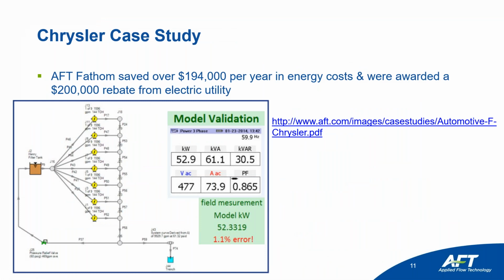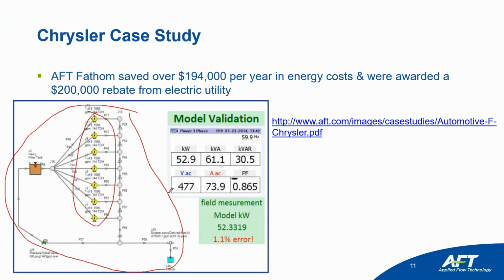Okay, so a few case studies that I want to go over. This is a case study that was done for the Chrysler plant in Michigan, in the United States, and they built a Fathom model of their piping system. It was for their cooling water system, and as you can see, it's a very, very simple model. Here are all their pumps that were operating, and what they did was lump their entire system into this general component right here with a resistance curve. So they were able to model the whole guts of their system in that little teeny piece. Ultimately, they found they were able to save $194,000 a year in energy costs, and they won a $200,000 rebate from their local energy utility.